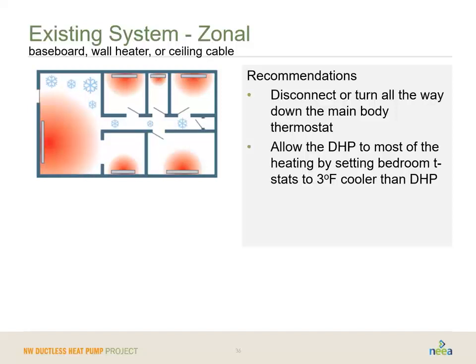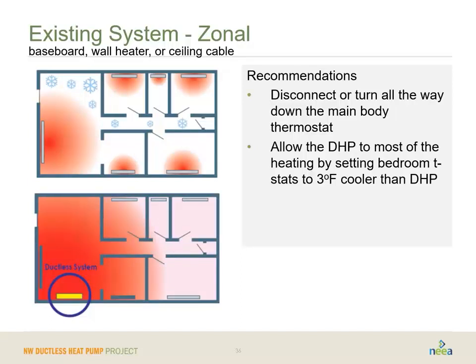And then allowing most of the other bedroom thermostats, set them 2 to 3 degrees cooler than the ductless heat pump. We do that so that slight variations in temperature throughout the house don't cause them to come on unnecessarily. It turns out most homeowners are fine with having their bedroom just a couple degrees cooler than the main body of the house. Again, I'm not talking about 5 degrees colder. I'm talking 2, 2.5, 3 degrees cooler. So setting those back is going to maximize your efficiency with these. This is really going to allow the ductless system to do the majority of the work.